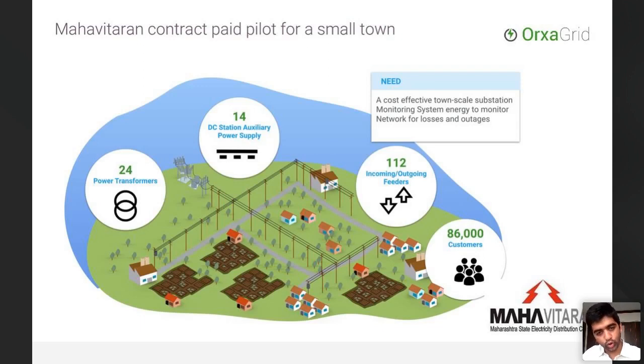So in discussion with Scope, Mahadiscom did a pilot project in a rural part of India, in a low network area zone, monitoring 14 substations. We monitored all the energy and digital status for incoming and outgoing feeders - these are 33 by 11 kV feeders - and power transformers, doing end-to-end transformer monitoring for each of the 24 power transformers, looking at transformer loading, winding temperature, oil temperature, OLTC status, and also DC monitoring of the substation battery banks.